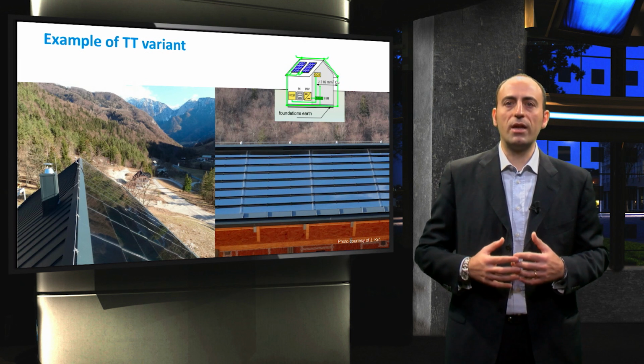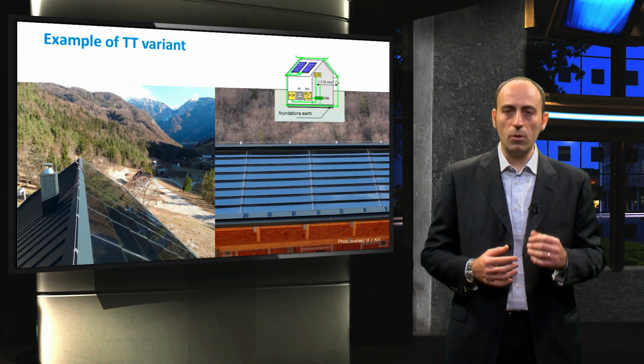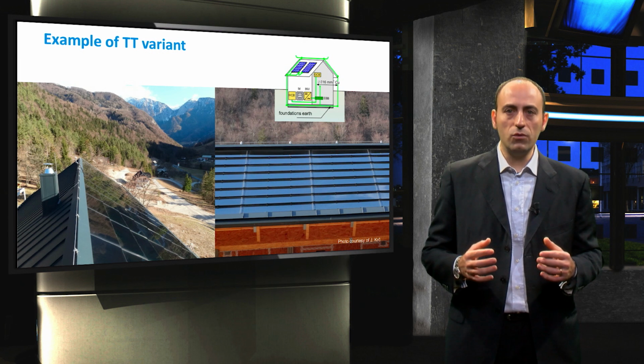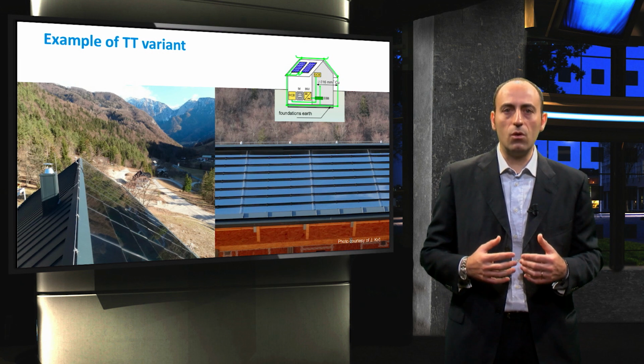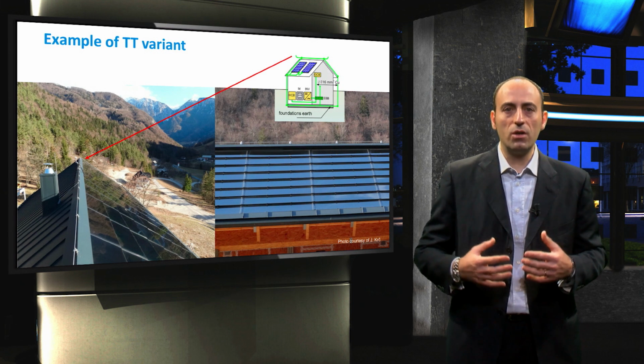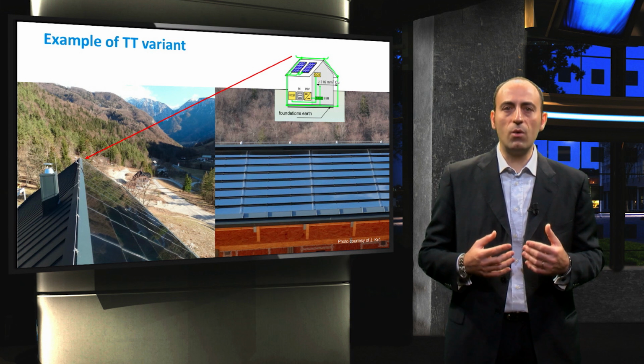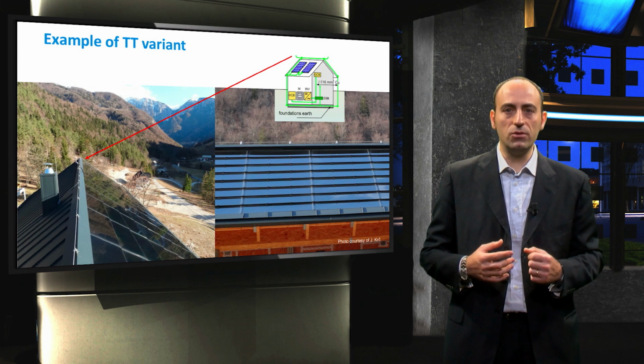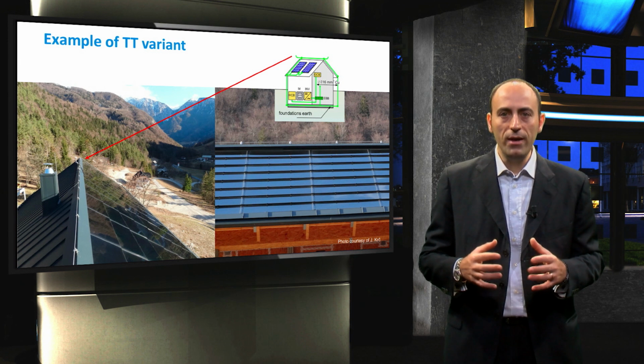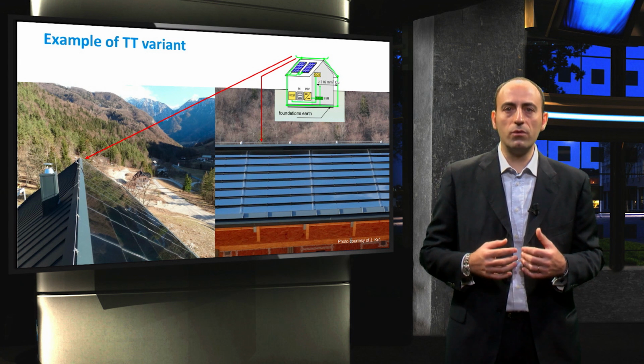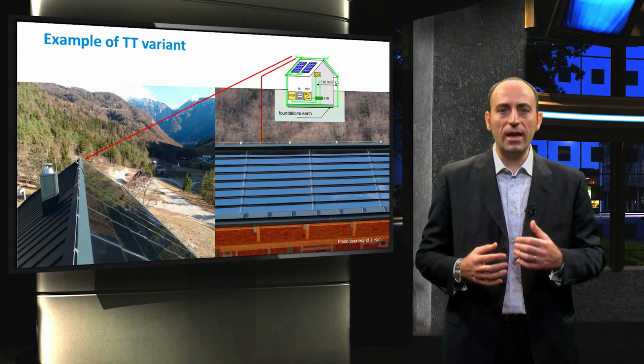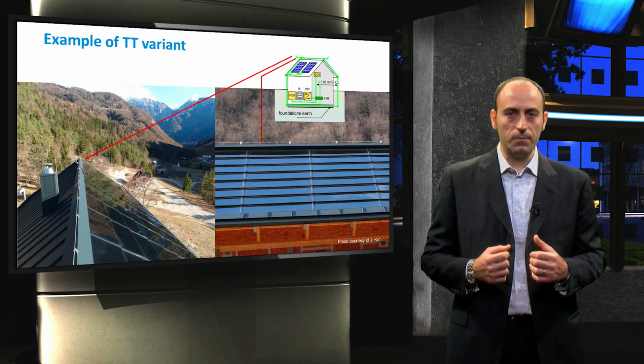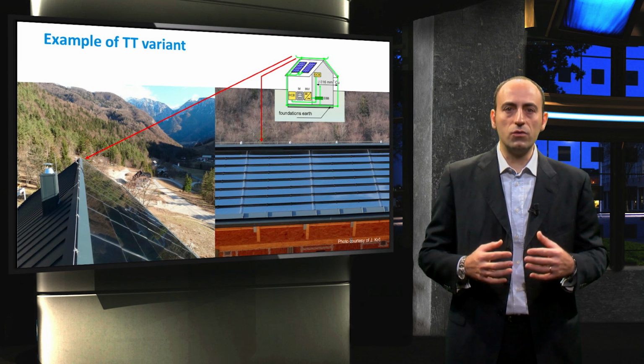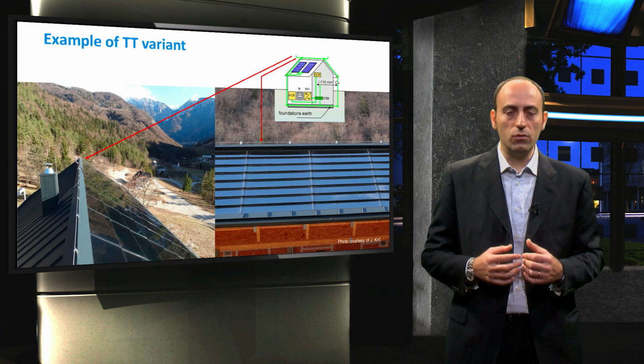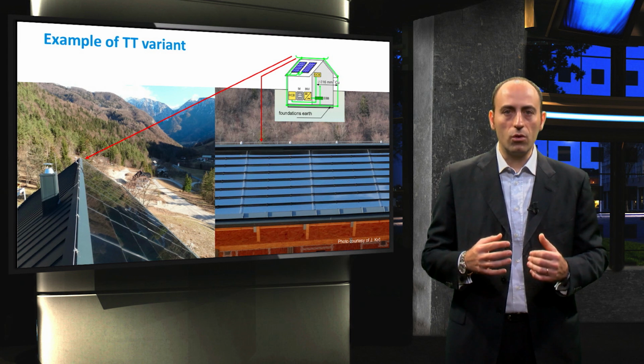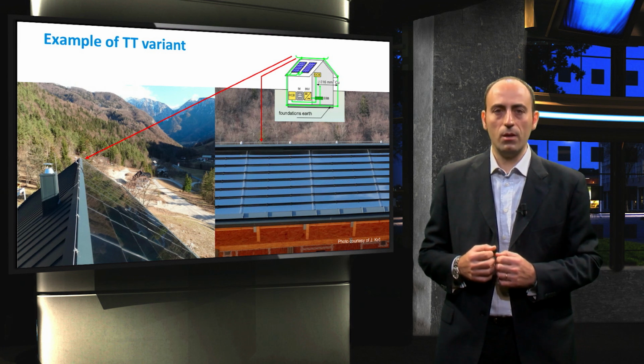Here, the lightning protection system is highlighted on top of the roof. At the edges of the roof, you may see the lightning rods or air terminals, which are vertical protrusions designed to act as a terminal for a lightning discharge. Then, rods are connected through conductor cables that carry lightning current from the rods to the ground. These cables run along the top and around the edges of the roof, then down 1 or more corners of the building to the ground.